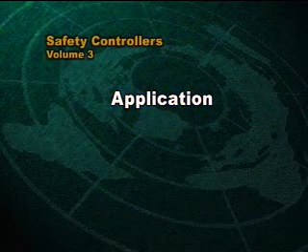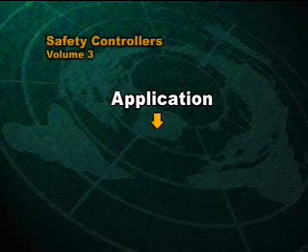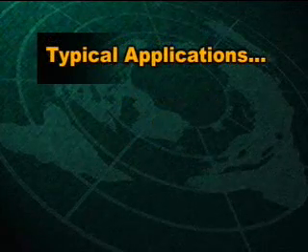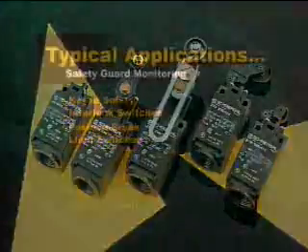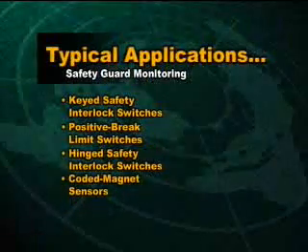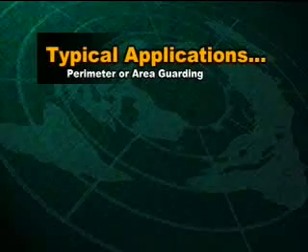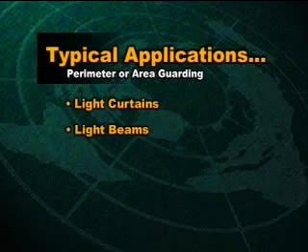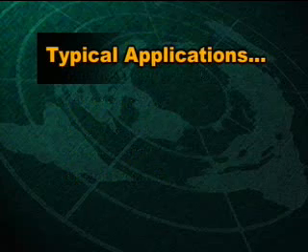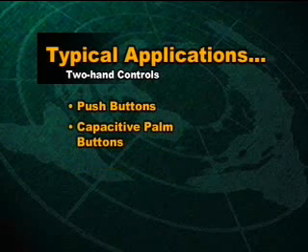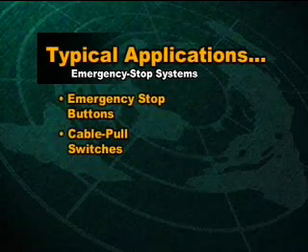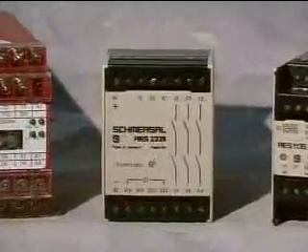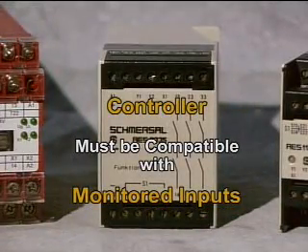We'll start with the type of safety application, which often dictates the type of safety system input components used. Typical safety applications include: movable safety guards using keyed safety interlock switches, positive-break limit switches, hinge safety interlock switches, coded magnet sensors, or safety edges; perimeter or area guarding using light curtains, light beams, pressure mats, or laser scanners; two-hand controls using push buttons, capacitive palm buttons, or optoelectronic sensors; and emergency stop systems using emergency stop buttons, cable pull switches, or safety edges. Different safety controllers are designed to work with these different types of input components, so the chosen safety controller must be compatible with the safety system's monitored inputs.